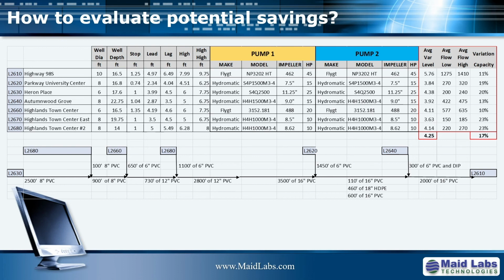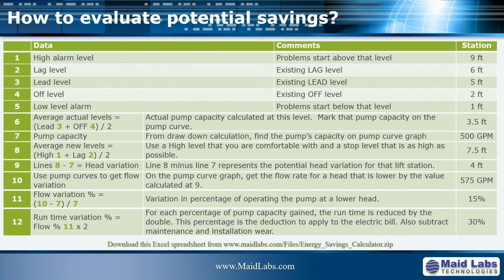So increasing the pump capacity means it will reduce the runtime by about 34% when the flow rate is low, which is most of the day, by the way. By reducing the pump runtime by 34%, the electrical costs, maintenance, and wear of everything are down by 34%. I made a spreadsheet to help you calculate what kind of benefits you could get out of your own lift stations. You can download it from the small link at the bottom here.